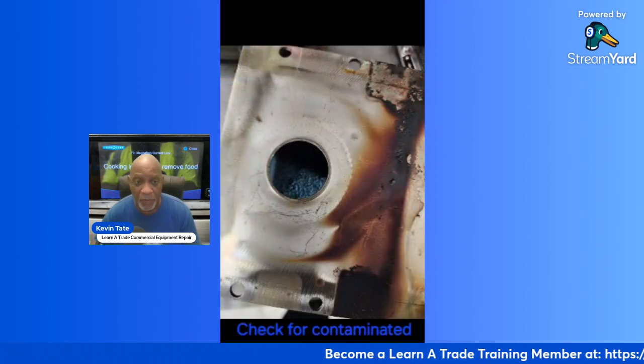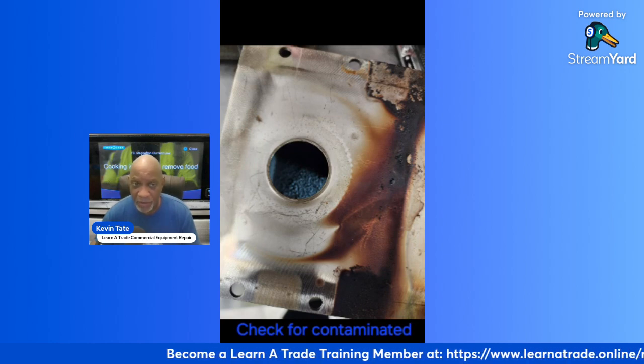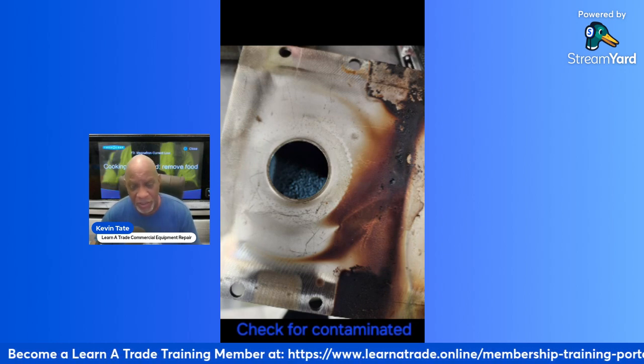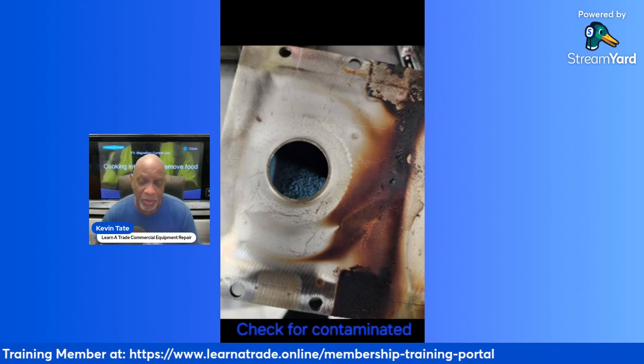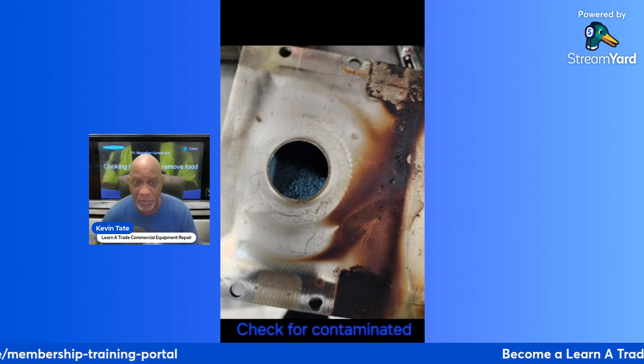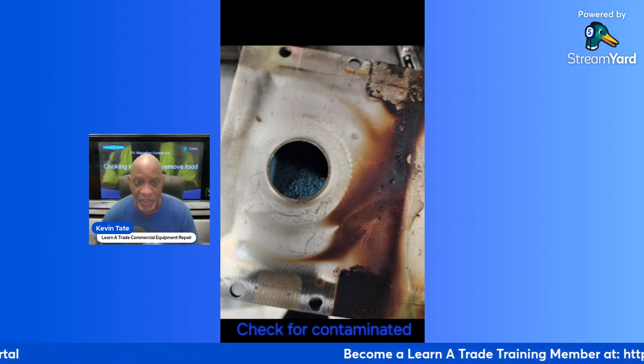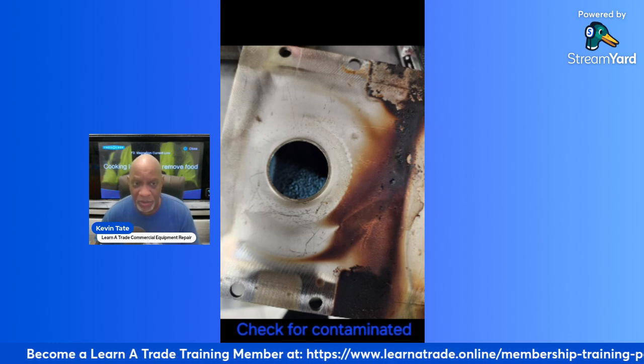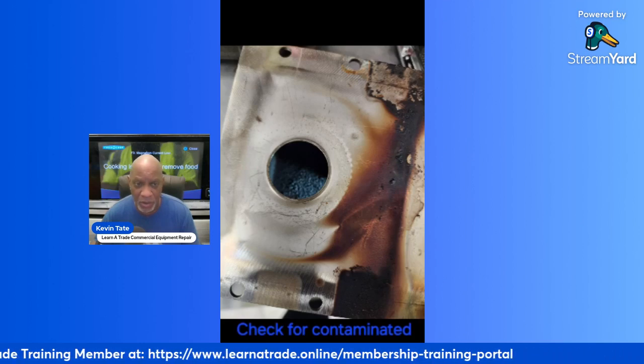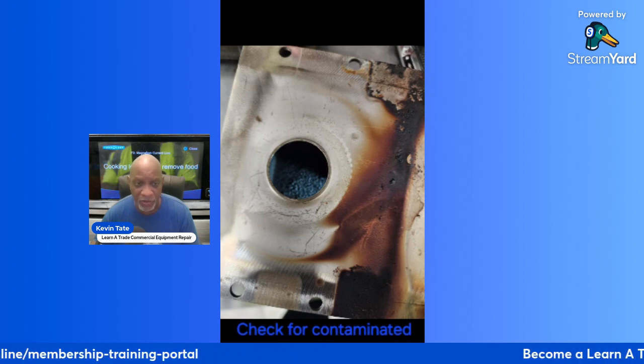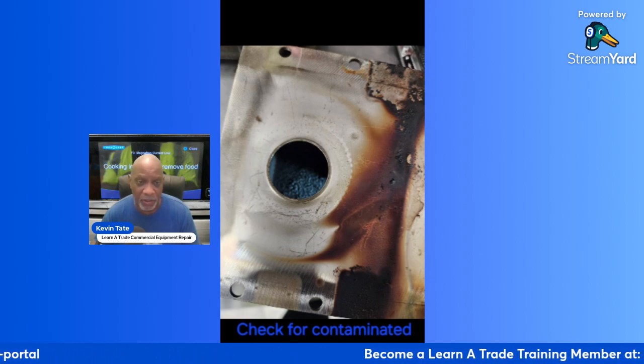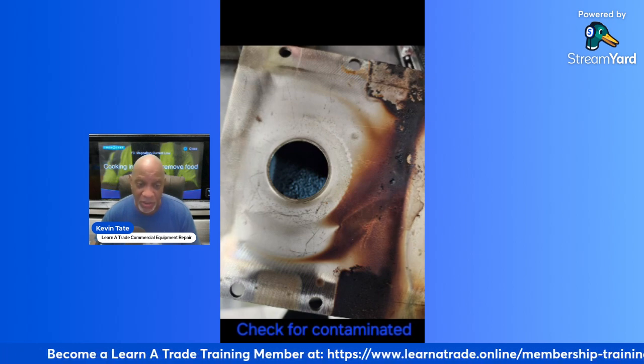Right here is a waveguide. This is a waveguide, and I'm showing you a picture of the inside of that waveguide. When you have a Mag 3 error, it's good to take your magnetrons off on both sides and use your flashlight to look inside that port, that opening on the waveguide. Because if you see it like this, you see how sooted up it is in there. It's like black. It's built up with grease, and it's just really built up in there, and that is going to cause the magnetrons to arc.